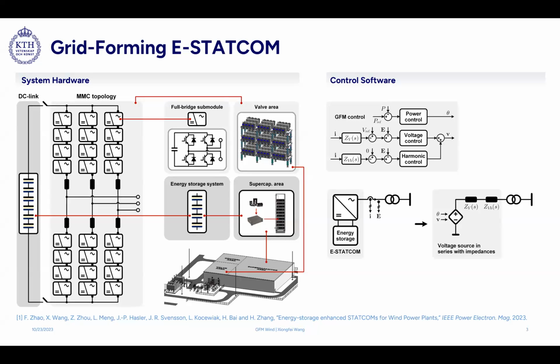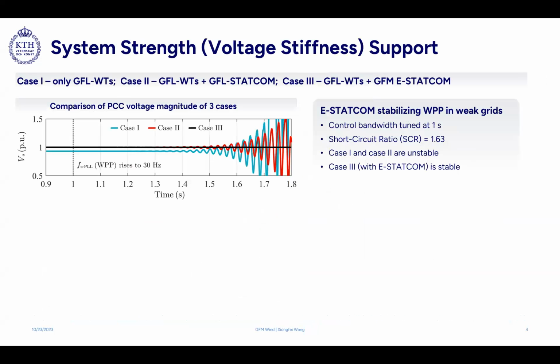So basically, we can say the E-STATCOM can be treated as a kind of voltage source in series with an impedance. This is aligned with our grid forming capability definition. Then let's look at the benefits. The first one is what we call system strength support. We enhance the voltage stiffness at the point of common coupling.